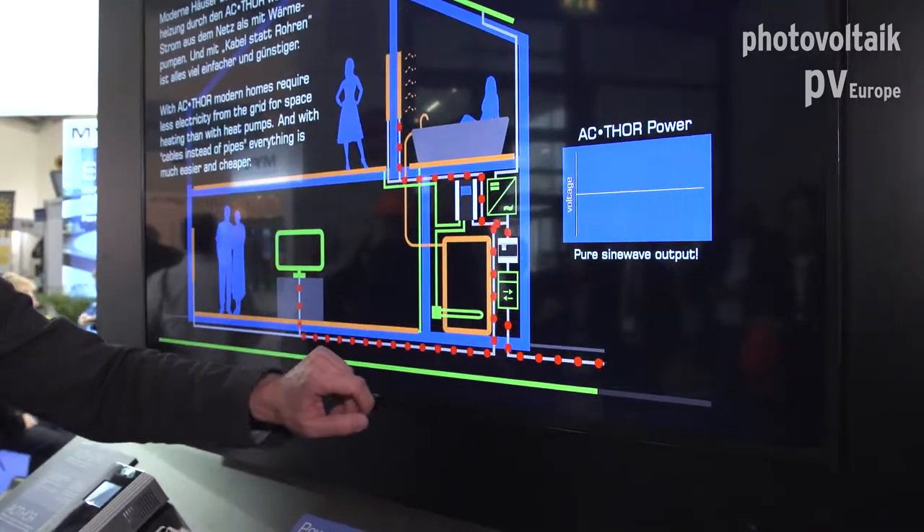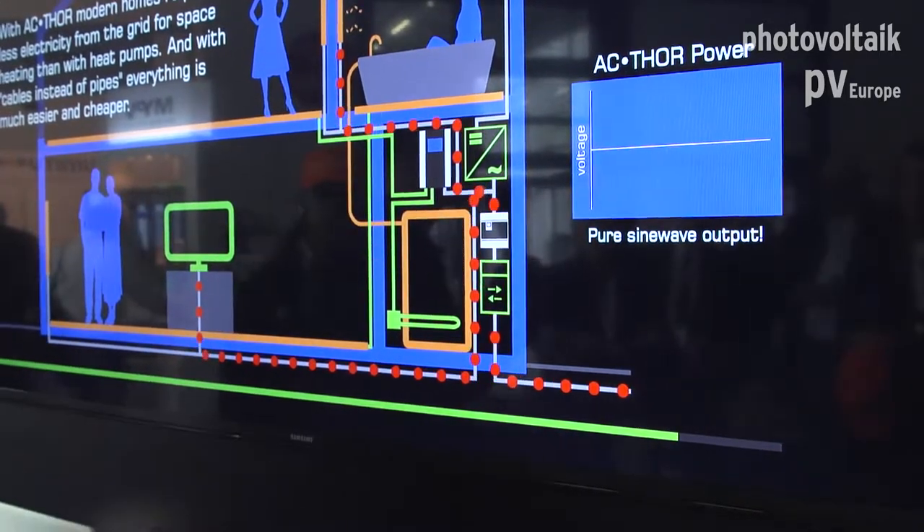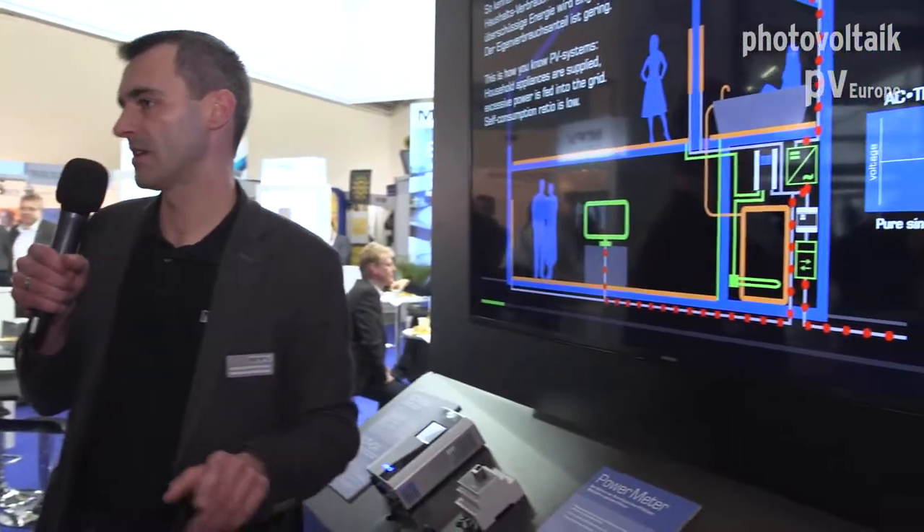The AC-THOR sets the power of the immersion heater to avoid feeding into the power grid and to avoid drawing from it, so the balance at the feed-in point is zero. This calculation and control is done very fast and accurately — once per second — and continues until hot water heating is complete.